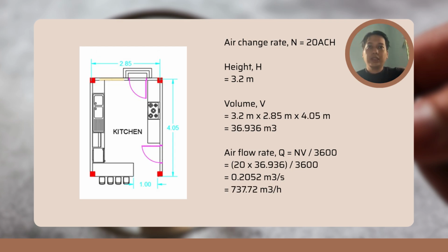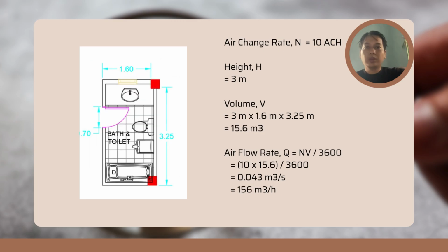The kitchen air change rate was 20 ACH, the height was 3.2 meter, the volume was 36.936 meter cube, and the airflow rate was 737.72 meter cube per hour. We moved to the upper level, which is the first floor. The air change rate was 10 ACH, the height was 3 meter, the volume was 15.6 meter cube, the airflow rate was 156 meter cube per hour.